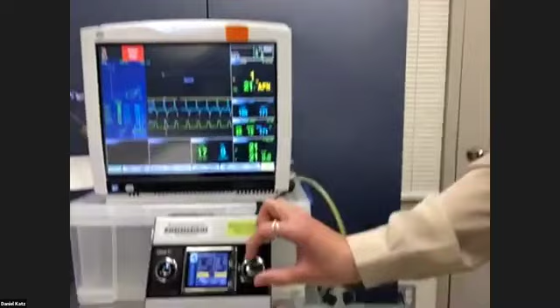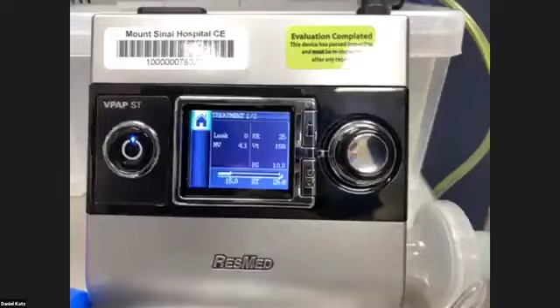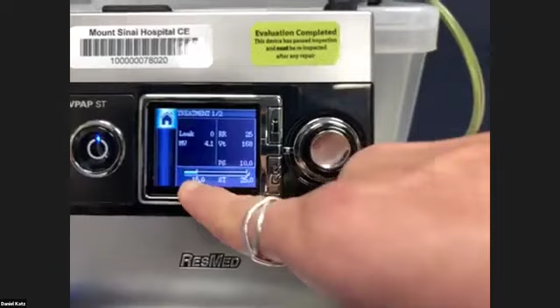So I just wanted to take everyone through the treatment screen, which is showing in real time the device set to bi-level ST mode, in which we have an expiratory PAP level, or EPAP level, that Dr. Poor previously referred to. This is equivalent to the PEEP. Above that, we have the IPAP level, which, on this particular ResMed device, can go up to a maximum of 25. The difference between the IPAP and the EPAP determines the driving pressure, or delta pressure, which here is shown by the PS, and that will determine the tidal volumes achieved based on the patient's lung compliance. So again, like pressure control ventilation.